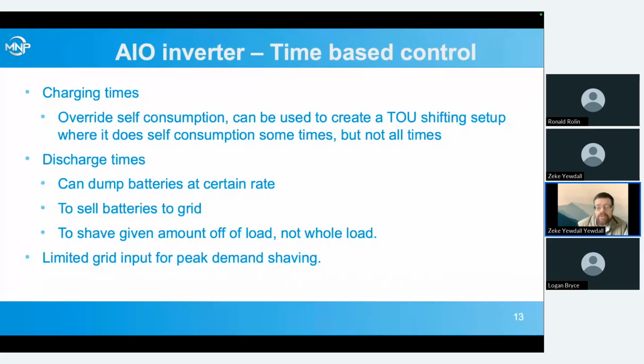So that's where you might set a discharge time and calculate it out so that you'll drain your batteries as much as you want by the end of that time period. But for general time of use, having self-consumption do it, because that'll just meet the loads rather than selling the batteries to the grid, is usually better.